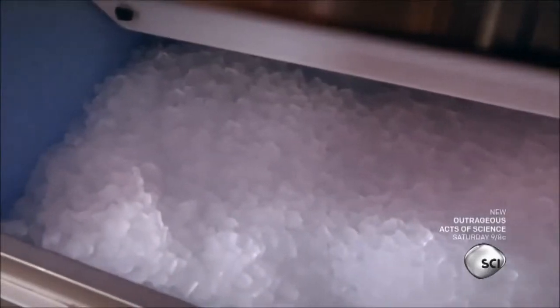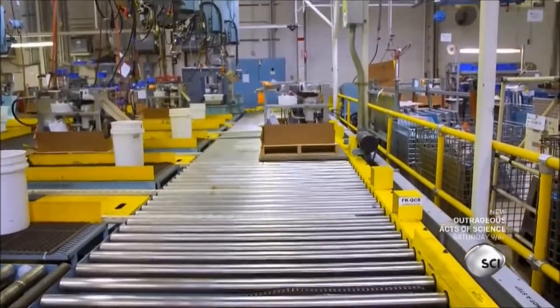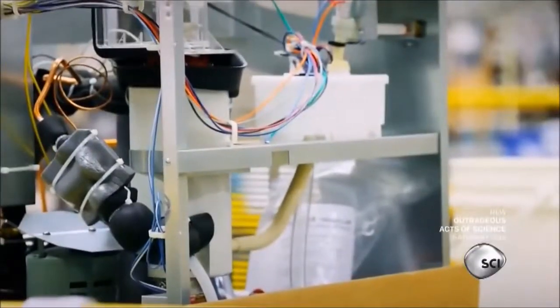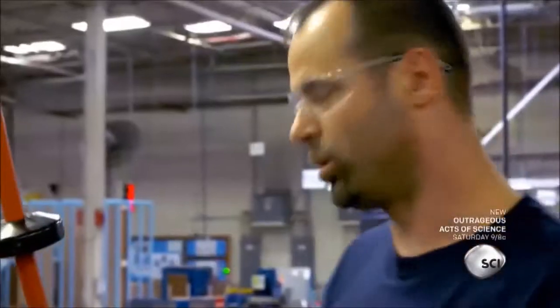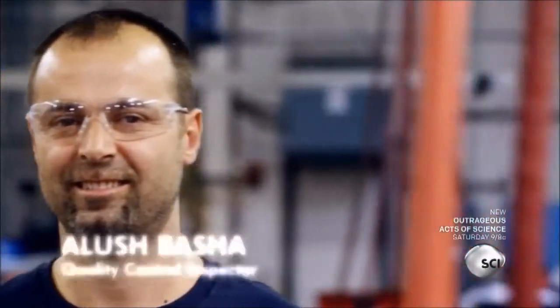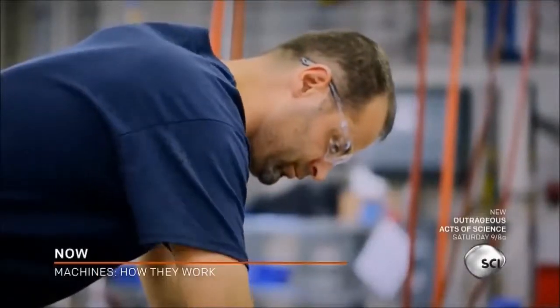And make sure you don't end up with a floor full of cubes. Workers must test the ice making mechanics of each device before it leaves the factory. Whatever machine comes here, we have to test. Alush puts every machine through a full ice cycle. It must produce ice in under two minutes.